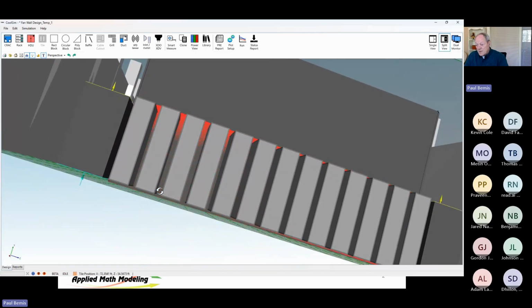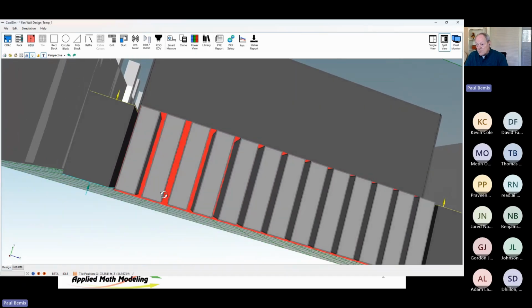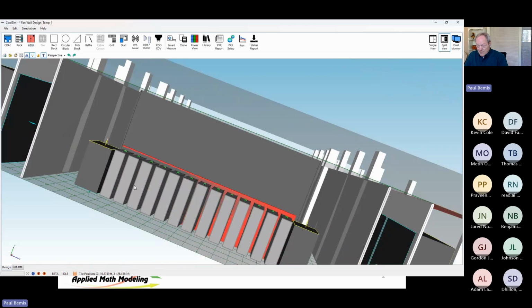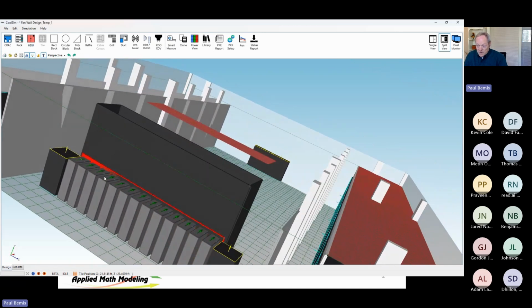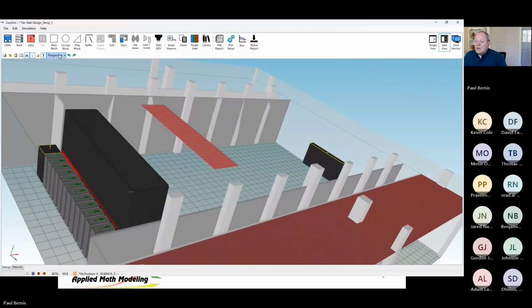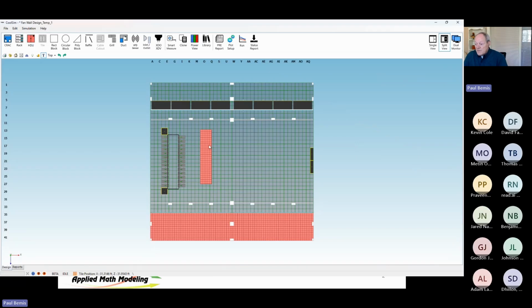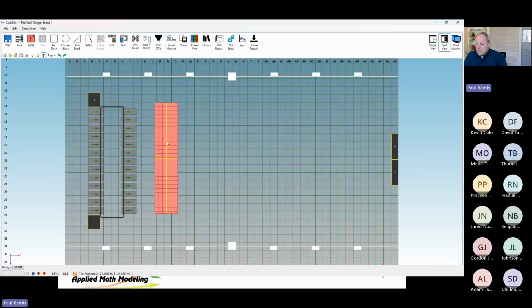It's defined. I'm up off the floor a little bit, so it's going to leak underneath. It's going to leak in between. If I have pressure problems in this room, it will show up. All right, and now I'm going to simply put in my ceiling grills. I have them over to the side so you can see them. I want those lined up too, so I'm going to line those up on this surface.